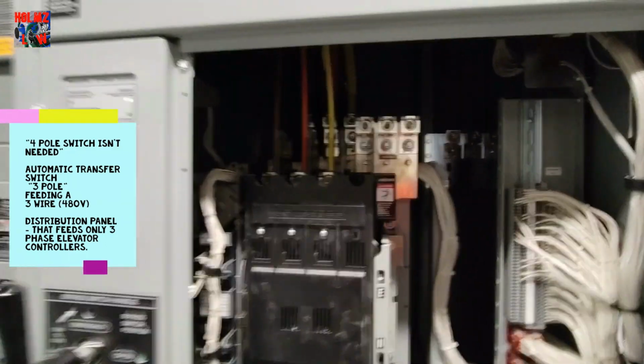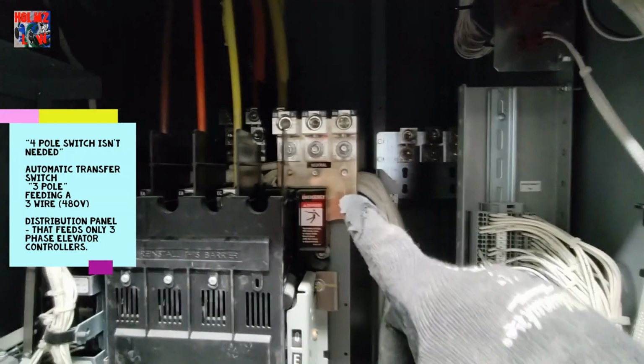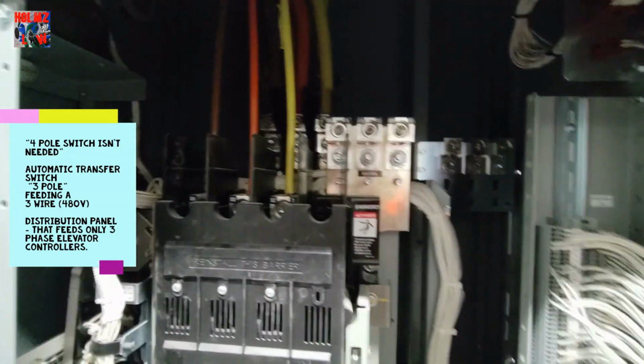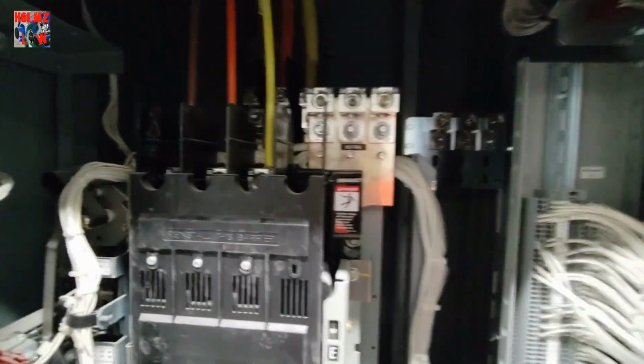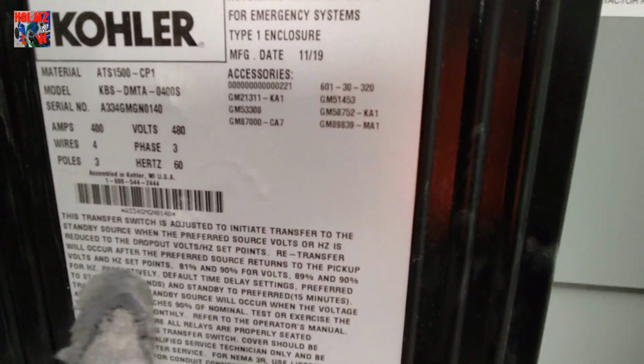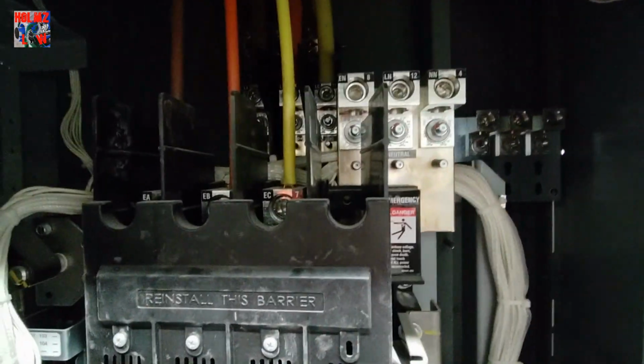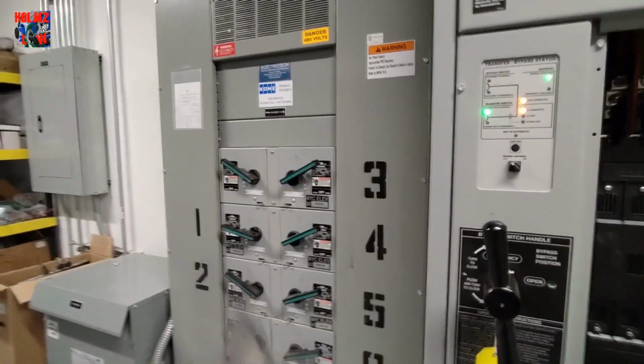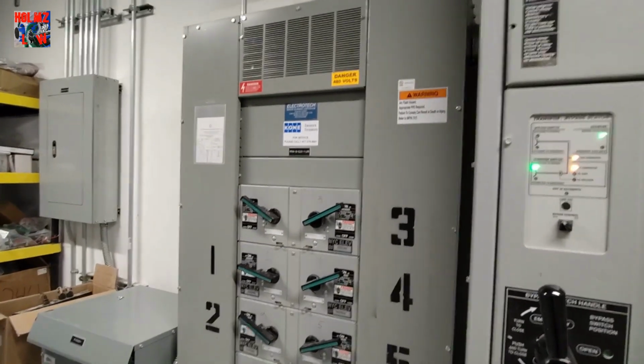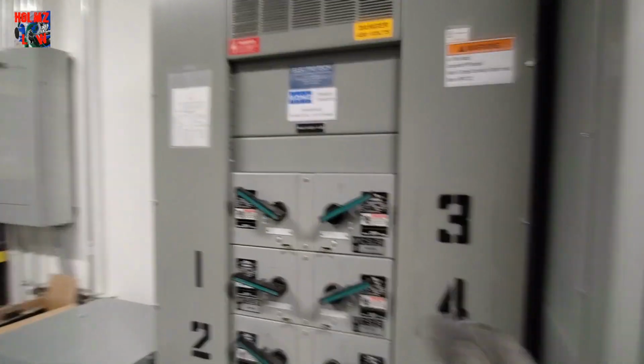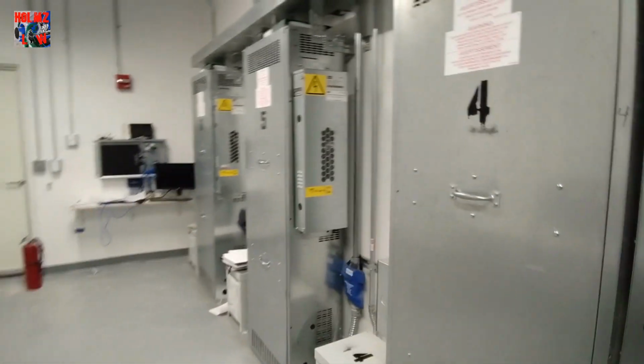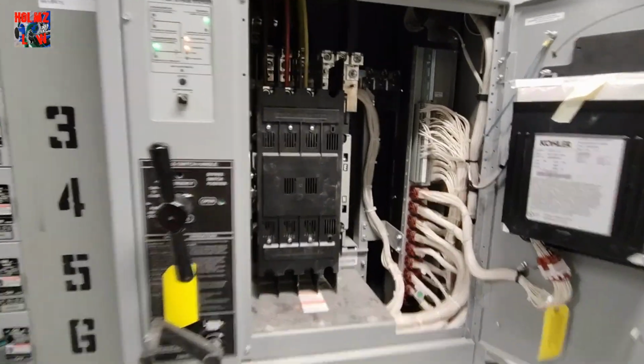This one here is a three-pole transfer switch, and it has a solid neutral, okay. But we don't need to worry about that in this case because this system here, we're not using the neutral at all. So it doesn't matter whether it's switched or not, okay. It's a 400 amp transfer switch, three-pole, four wires, okay. Obviously, we don't have the neutral here, okay, and yeah, it's a three-phase load that we're actually feeding here, okay. This distribution panel is only feeding three-phase loads, so we don't have a neutral coming to this distribution panel. It's only feeding three-phase controllers for the elevators, okay, so we don't have to worry about the neutral being switched or not because we have no neutral in this system here.